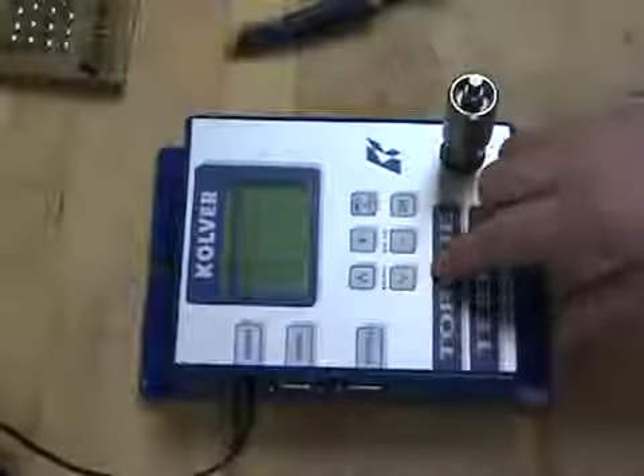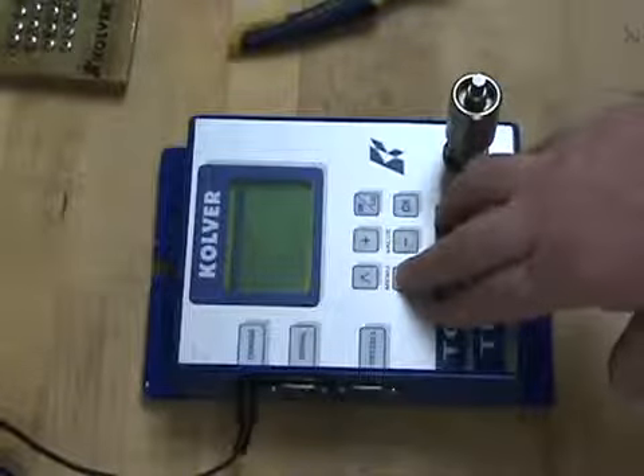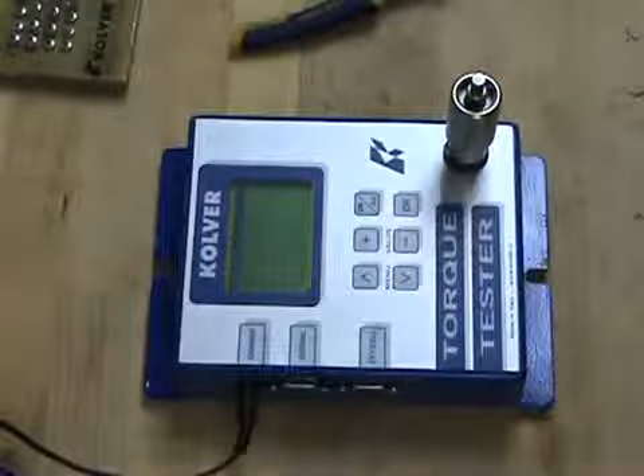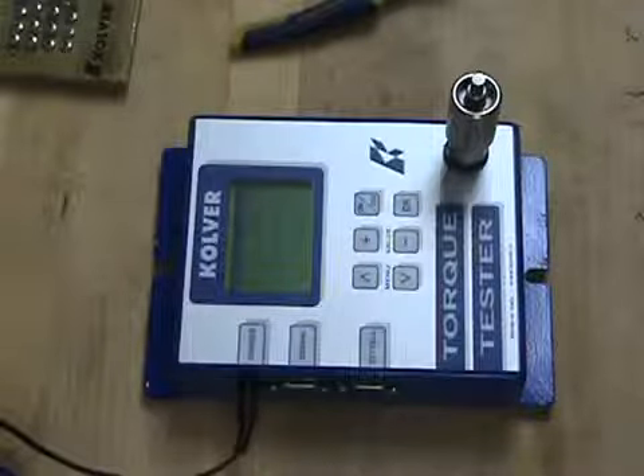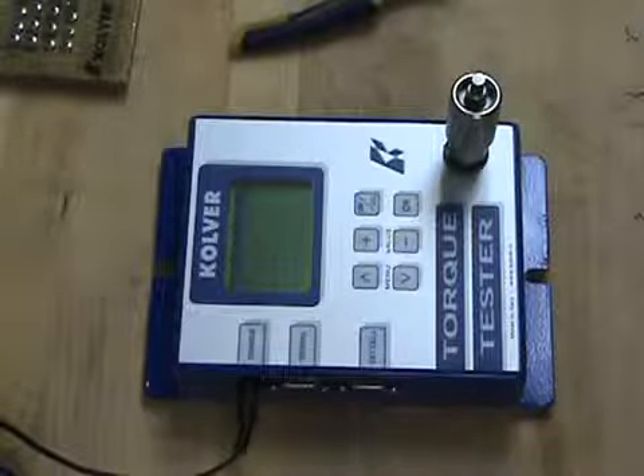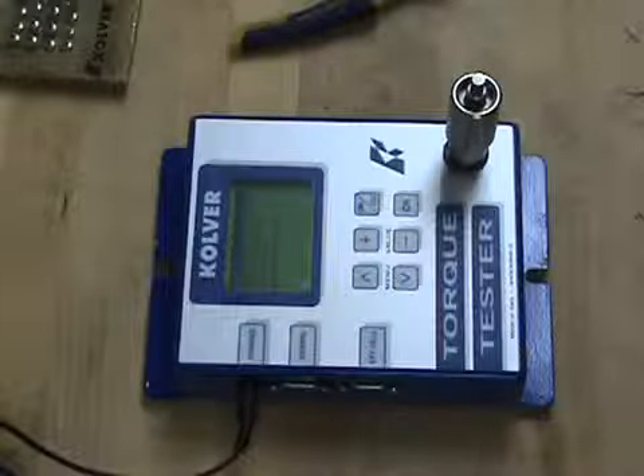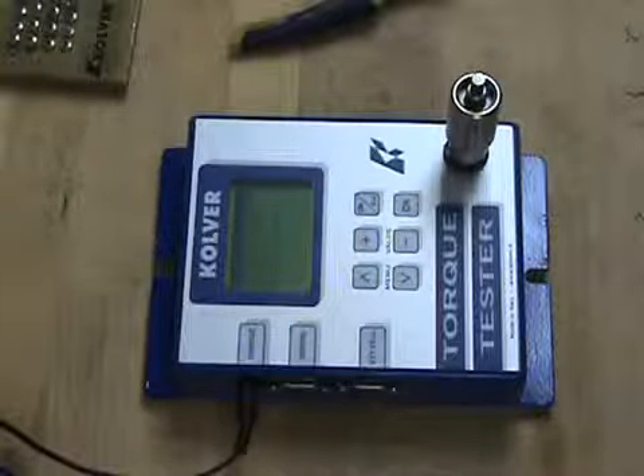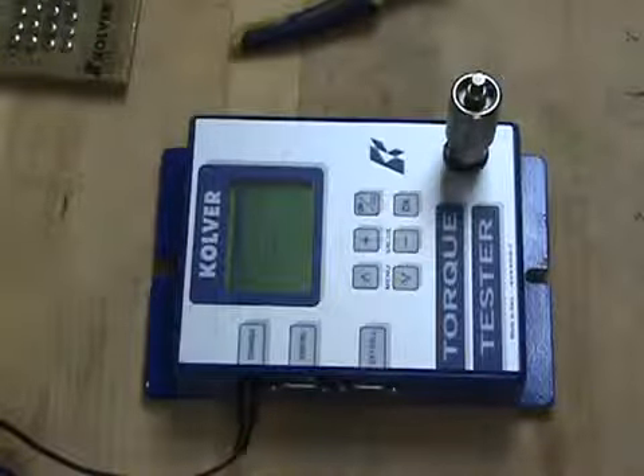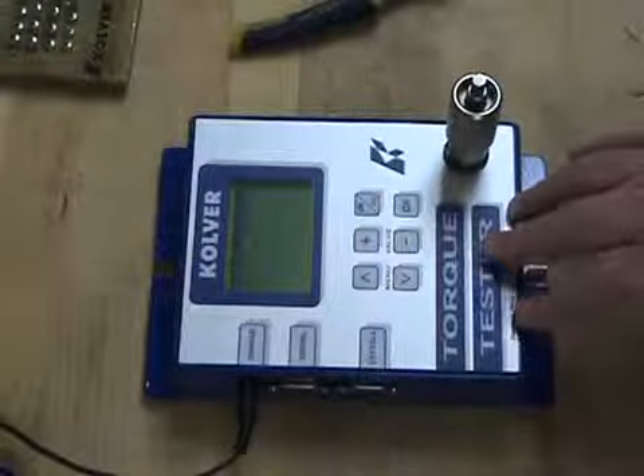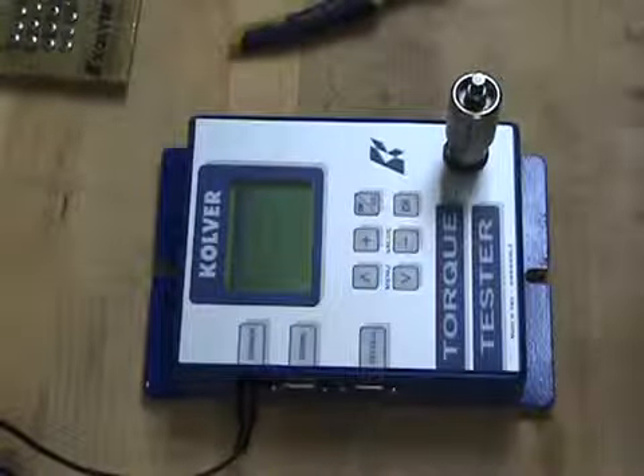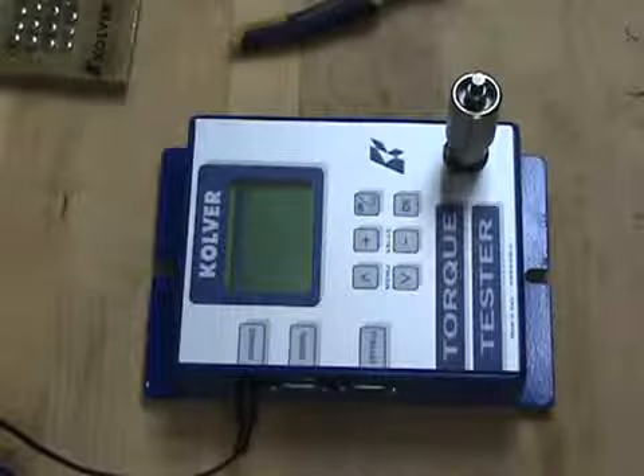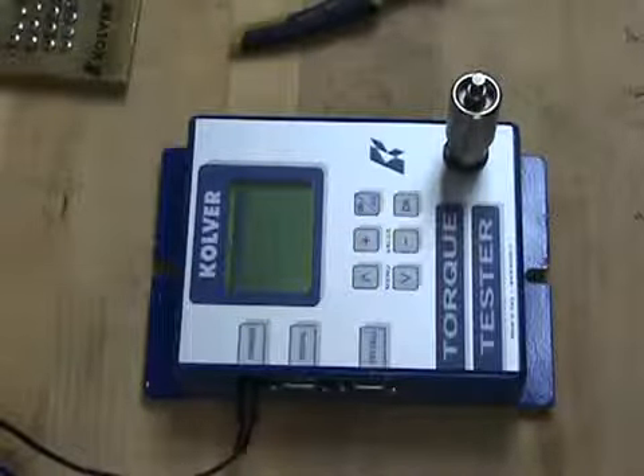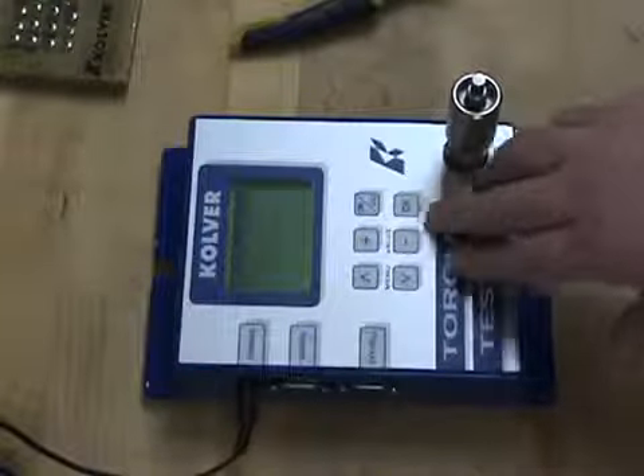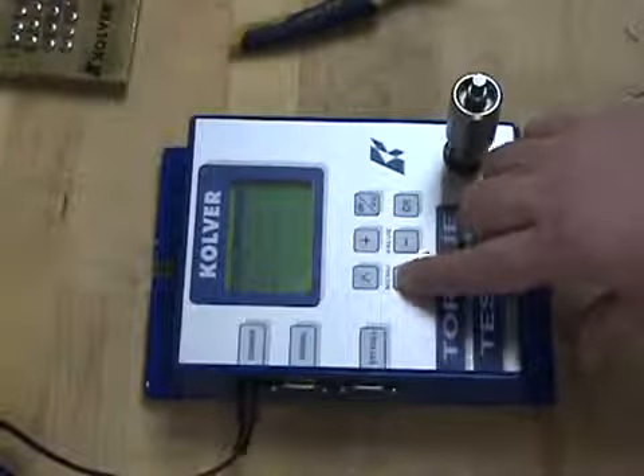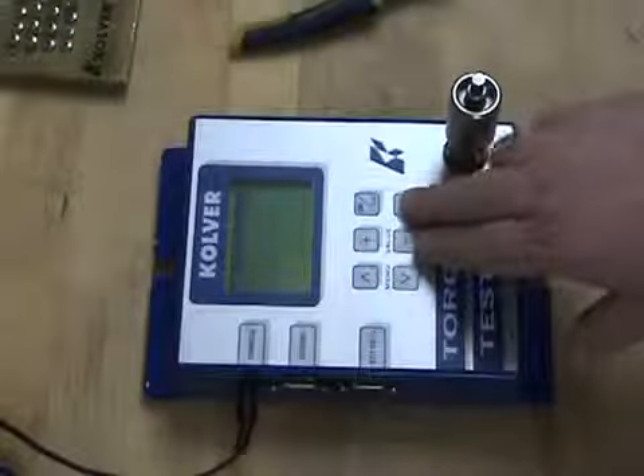Okay, back to our original menu, and we're going to memory. We can store up to 500 readings. So you can go out onto the production floor and do a set of rundowns and go back to your office and download that memory. If you press the print feature while it's connected to the serial port, it will either print to a serially connected printer or to your computer if you have it set up to receive. We can also look at the number of rundowns that are in the unit. It will actually give you an average.